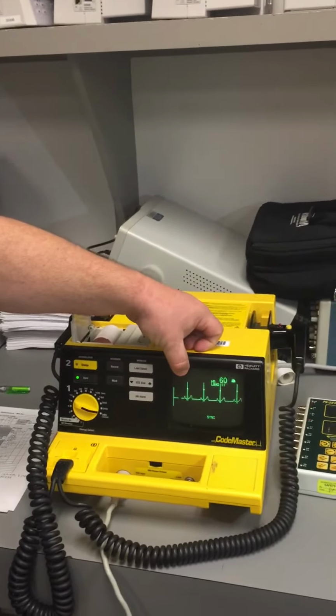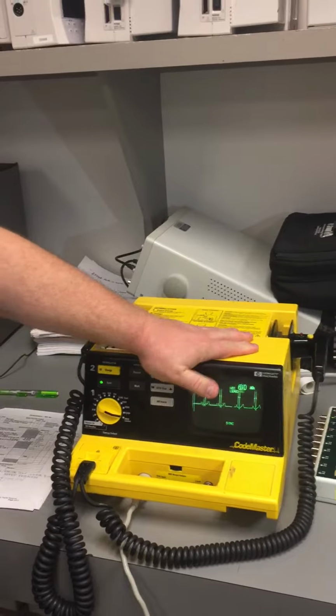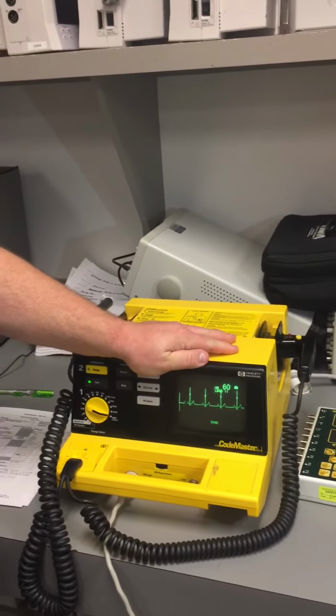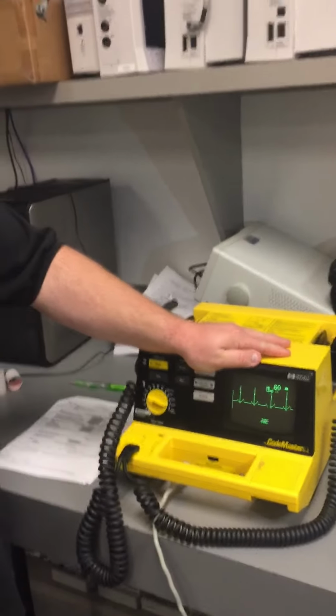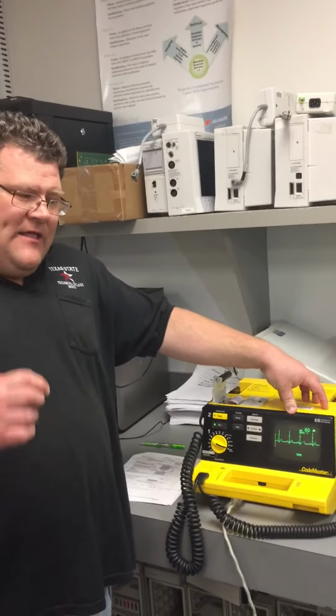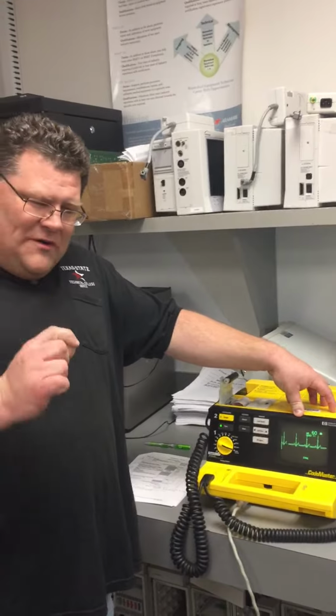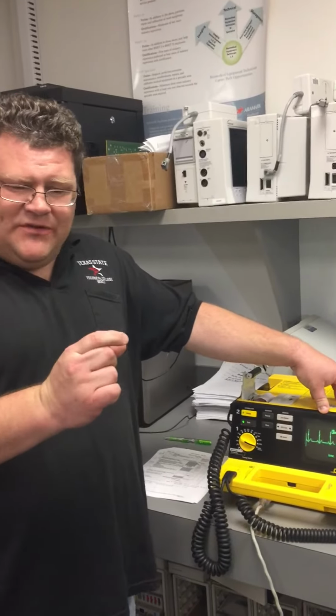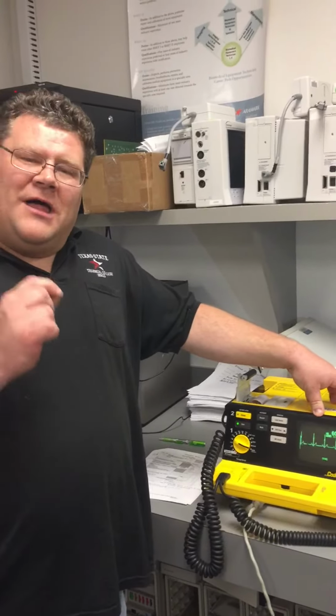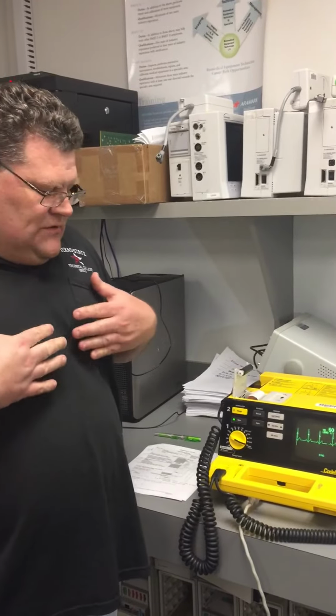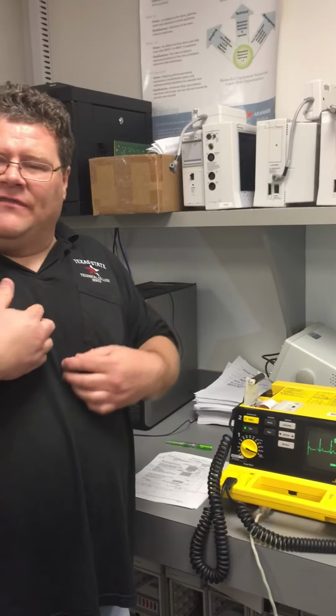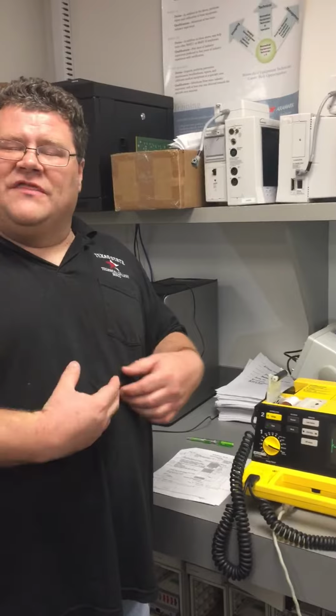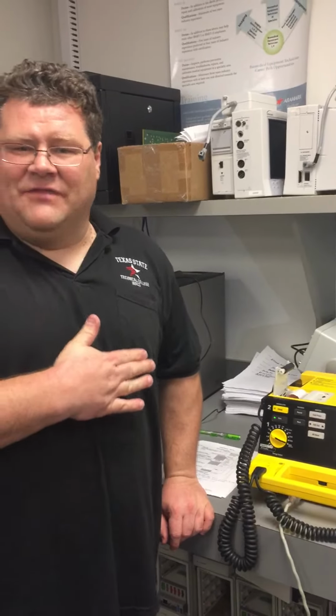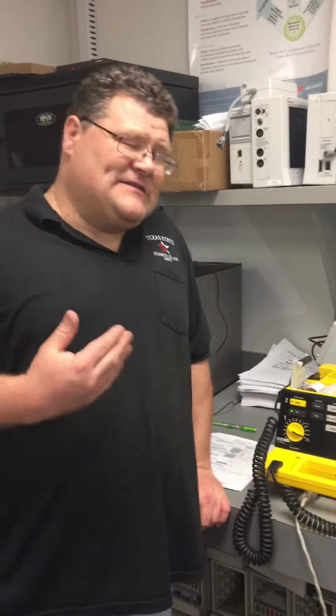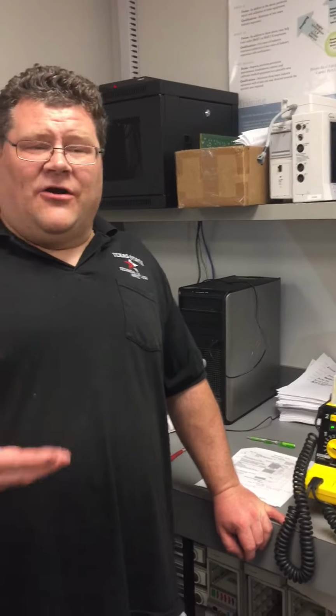So what we're going to do is we're actually going to fire the defib at 20 to 30 milliseconds after the peak of the R wave. Now this is a sweet spot, for lack of a better term. That point, that one small 10 millisecond window, will allow us to take out a spasm on the top portion of the heart without affecting the operation of the bottom portion of the heart.